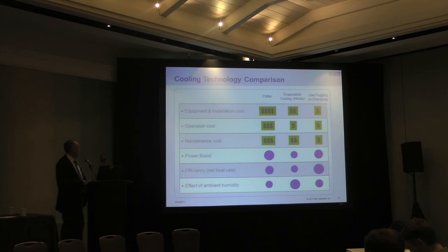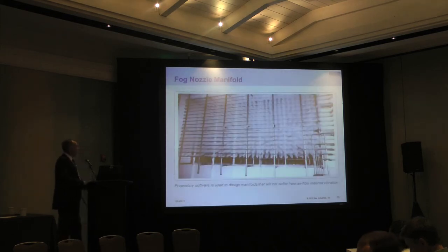So economically, probably, in terms of efficiency, if you take water into account, it's kind of a wash between those two. And the effect of ambient humidity, again, people tend to think that fogging is highly affected by humidity, as evaporative cooling is. But if you do overspray fogging, you can still get a very large power boost in a humid environment. This shows a typical nozzle array.